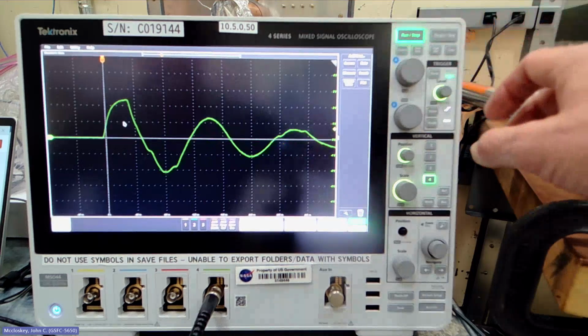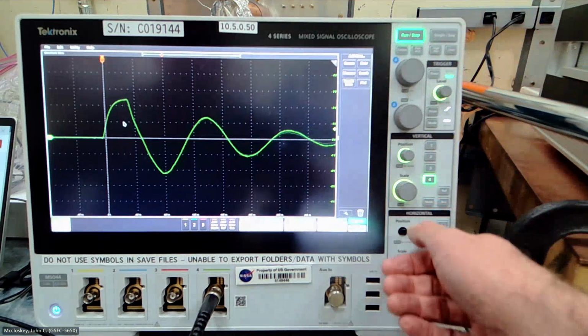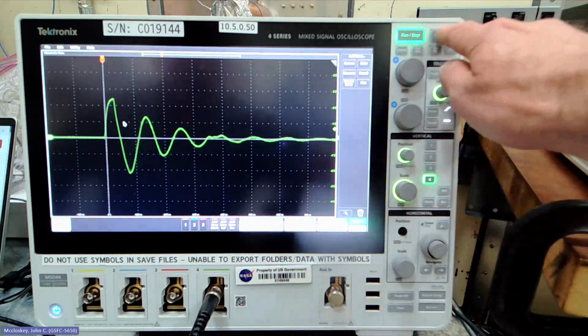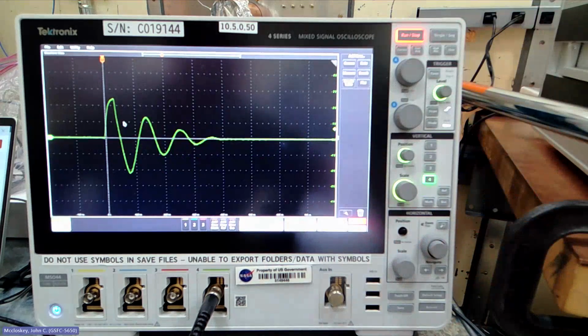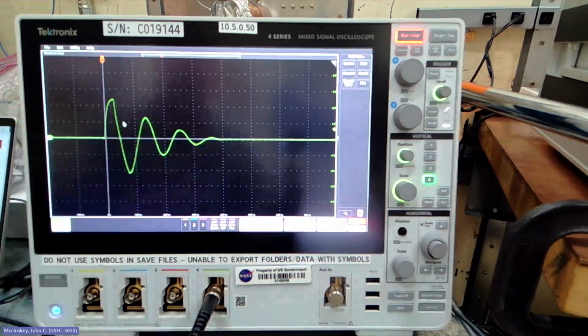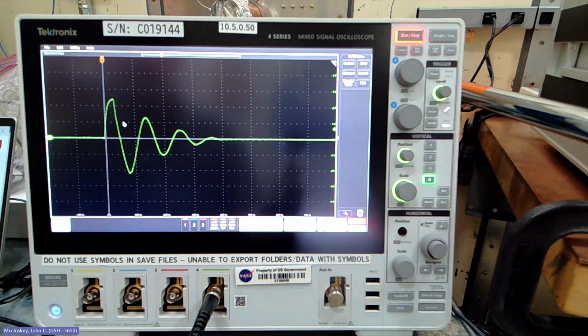Turn the signal back on, and now get a single trigger here. There we go. That's about as good as that's going to look. That's clearly a damped sinusoid kind of response. That is the natural response of this cable configuration to that stimulus.